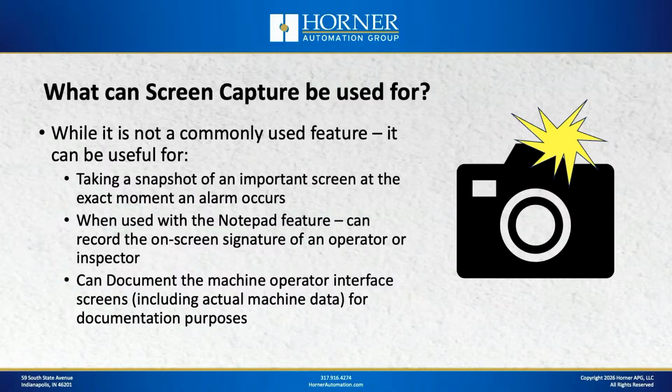For instance, I've seen it used where a customer has a particular alarm that when they detect that alarm in their logic, they not only trigger an alarm through the alarm feature in the Horner OCS, but they also trigger a screen capture of a particularly key screen that is showing machine parameters. That way, not only do they, of course, have the time and date that the alarm occurred through the alarm feature, but they also have an image they can go back and look at that captures what was going on the machine at that time.